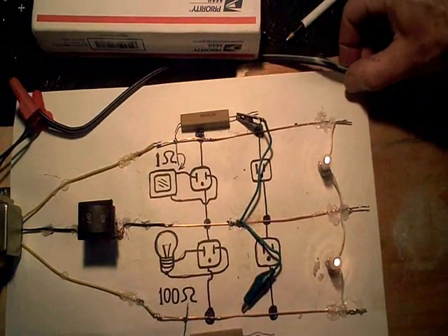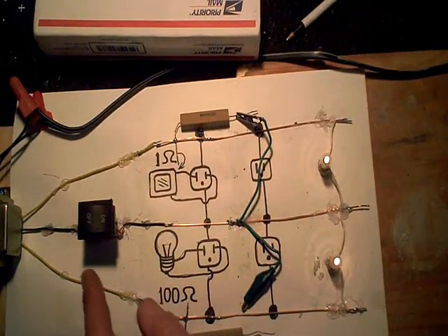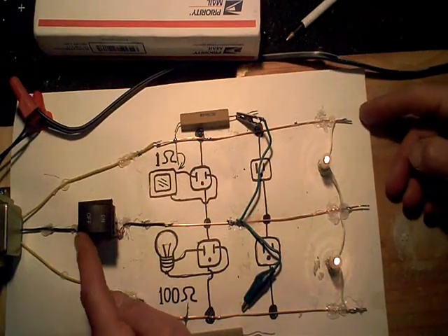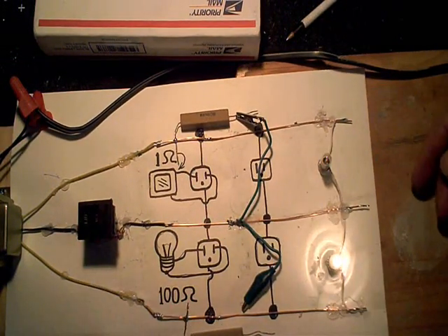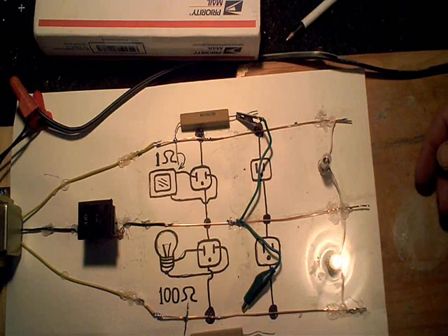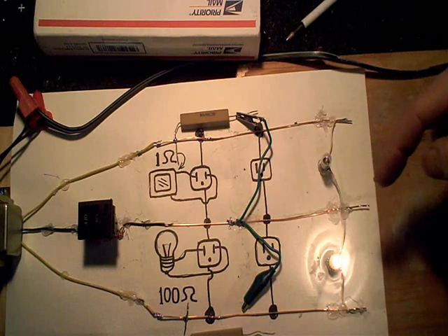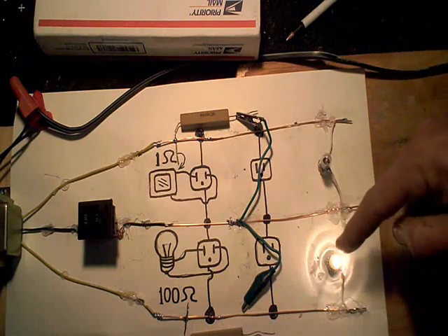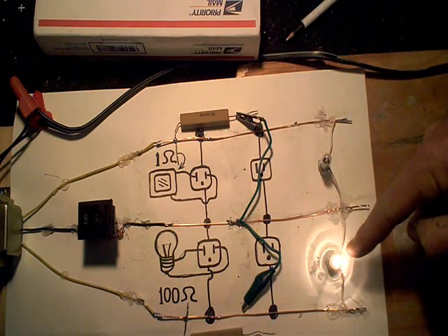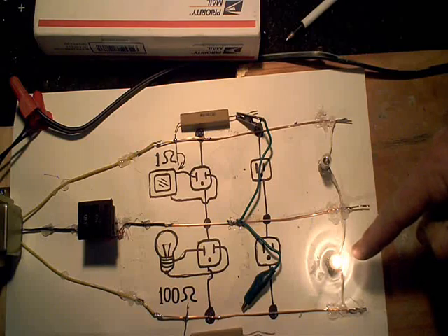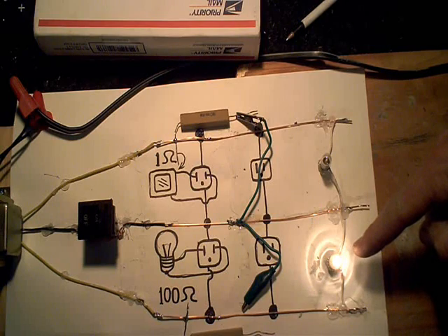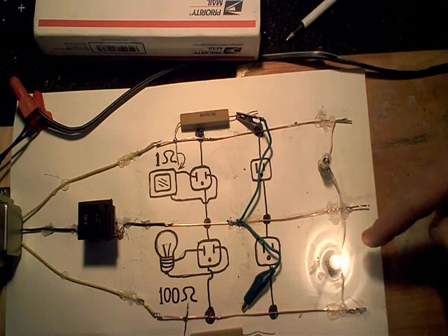Now, everything seems to be running fine, but watch what happens when I break the neutral wire. When I break the neutral wire, now you're getting a much higher voltage going into this lamp here, and that's how it is that the TVs were damaged that were brought in the shop.